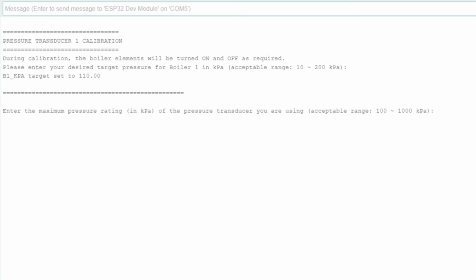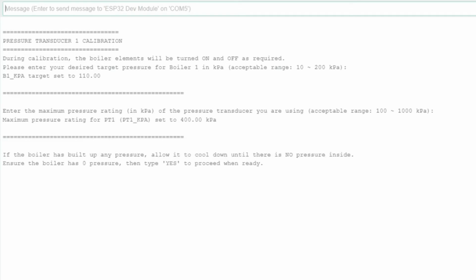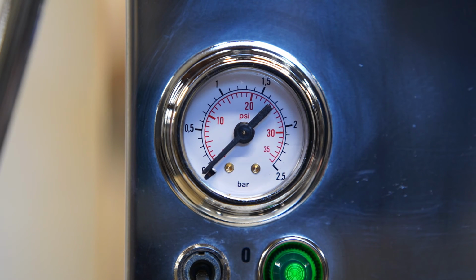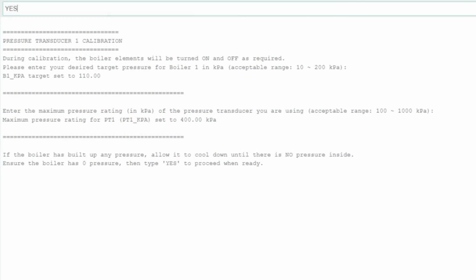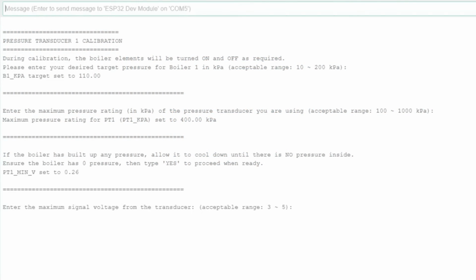Next, the wizard needs to know the maximum pressure rating of the transducer. In my case, this value is 400 kPa. Now the wizard is asking me, if the boiler is pressurized, wait until the boiler cools down and there is no pressure. Since my boiler is cold, I can proceed, and the wizard measures the voltage signal at 0 kPa and uses this as a reference for later. Now we are asked for the maximum signal voltage, which in my example is 4.5.